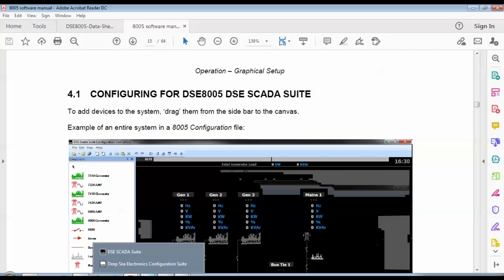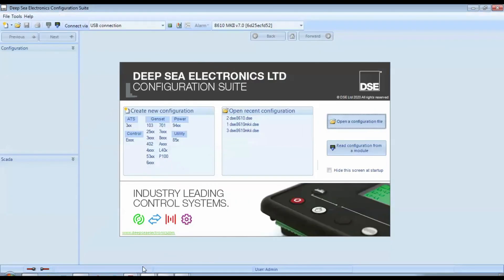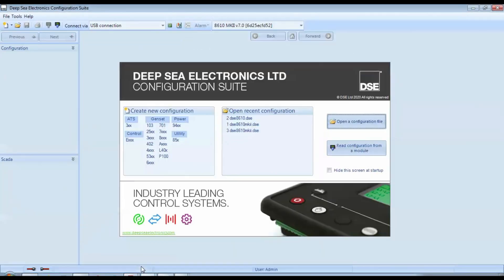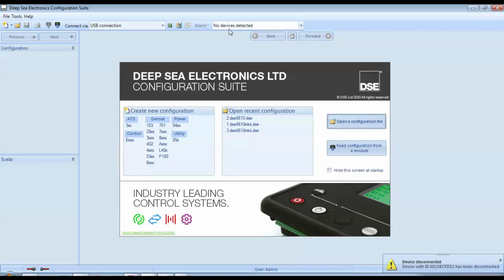Step 1: Setting IP Addresses in Controllers. First of all, we need to set IP addresses in the controllers. For this, we use the Deepsea Electronics Configuration Suite software. I have connected one controller to my laptop using a USB cable. One end of the USB cable is connected to the 8610 controller, and the other end is connected to the laptop running the Configuration Suite software.